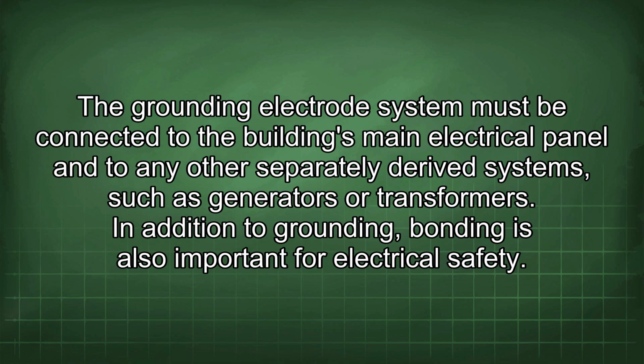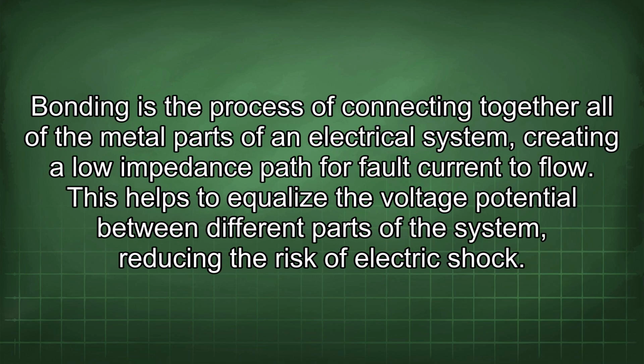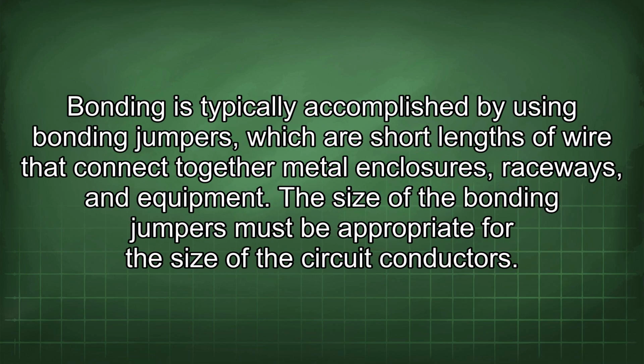In addition to grounding, bonding is also important for electrical safety. Bonding is the process of connecting together all of the metal parts of an electrical system, creating a low impedance path for fault current to flow. This helps to equalize the voltage potential between different parts of the system, reducing the risk of electric shock. Bonding is typically accomplished by using bonding jumpers, which are short lengths of wire that connect together metal enclosures, raceways, and equipment. The size of the bonding jumpers must be appropriate for the size of the circuit conductors.